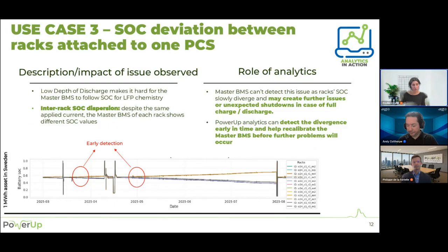And these values tend to diverge more and more because they are not detected immediately by the BMS, since it's a slow divergence, not just a peak. So it's really something slow and it's not detected. And in this situation, each rack has its own value.